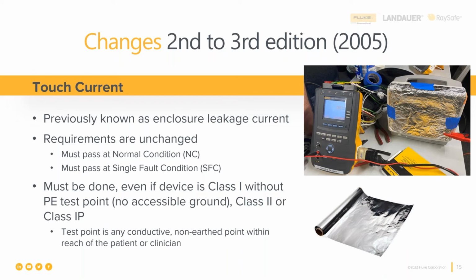The way the standards tell us to do this test is to use aluminum foil, tape it down, and connect our test lead to the aluminum foil. Well, let's talk about why that is. First of all, we need to recognize human beings are all conductors. We are not insulators when it comes to electrical current flow.